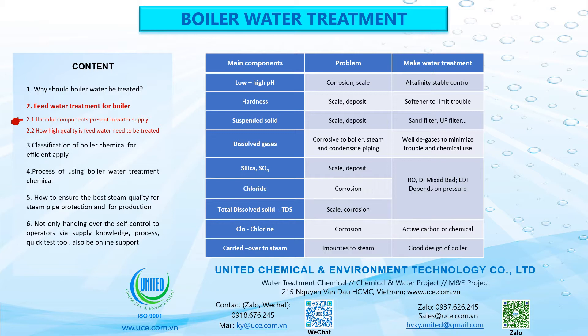2. Main component: Hardness. Problem: scale and deposit. Water treatment should include a softener to limit trouble. 3. Main component: Suspended solids. Problem: scale and deposit. Water treatment should include sand filter or UF filter. 4. Main component: Dissolved gases. Problem: corrosive to boiler, steam and condensate piping. Water treatment should include degassing to minimize trouble and chemical use.